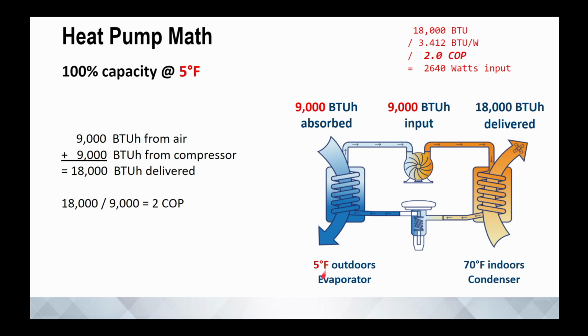Okay, well that's at 5 degrees outdoor temperature. That's pretty good, right? We're 200% efficient at 5 degrees. Well, here's how it basically boils down, the math, right? 18,000 divided by 9,000 input. 18,000 output divided by 9,000 input is a COP of 2 or 200%. Here's your watts if you really want to dig into that. And that's great. That's a piece of equipment that's at 100% capacity at 5 degrees, operating at 200% efficient.